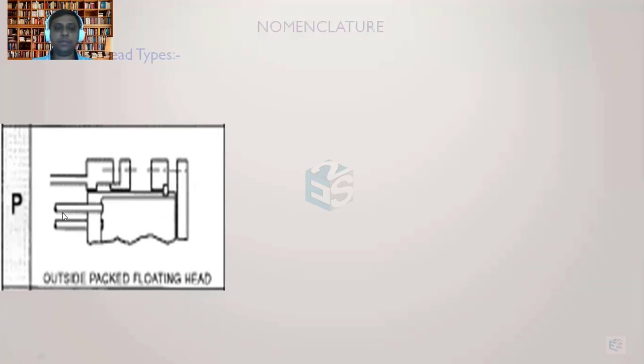When there is a high temperature difference, the tubes expand and move to the right side. Since the tubes are attached to the tube sheet, and the tube sheet is integral with the channel shell, this entire assembly moves. The channel shell is also attached to a blind cover, which is free — it can be removed and tightened with bolting.